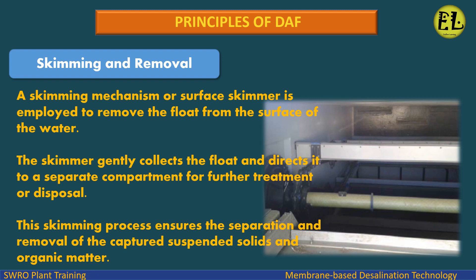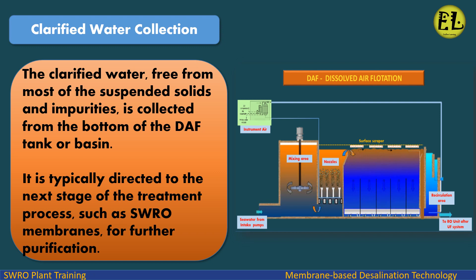Skimming and removal: A skimming mechanism or surface skimmer is employed to remove the float from the surface of the water. The skimmer gently collects the float and directs it to a separate compartment for further treatment or disposal. This skimming process ensures the separation and removal of the captured suspended solids and organic matter. The clarified water, free from most of the suspended solids and impurities, is collected from the bottom of the DAF tank or basin, and is typically directed to the next stage of the treatment process, such as SWRO membranes, for further purification.